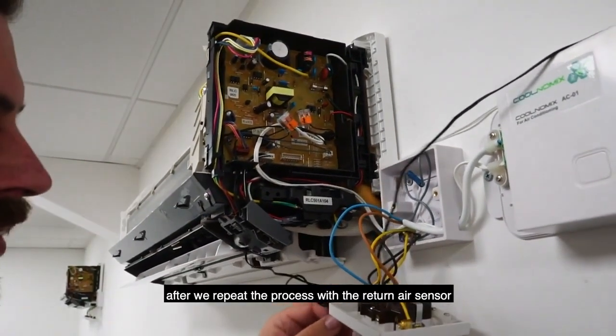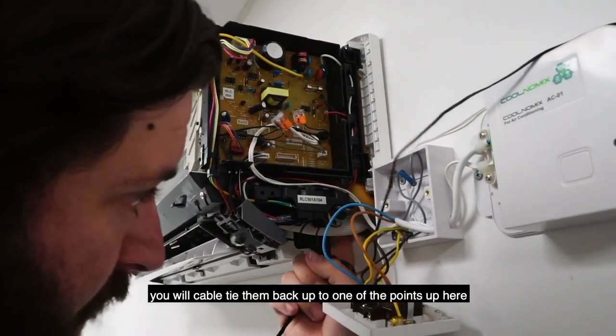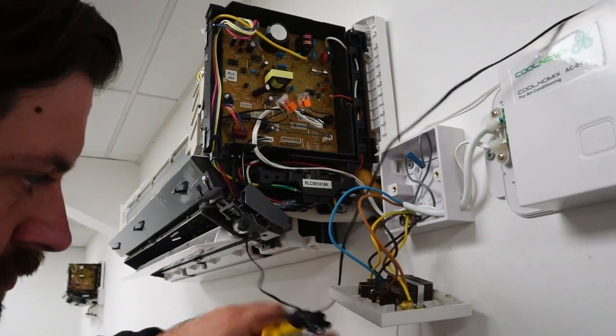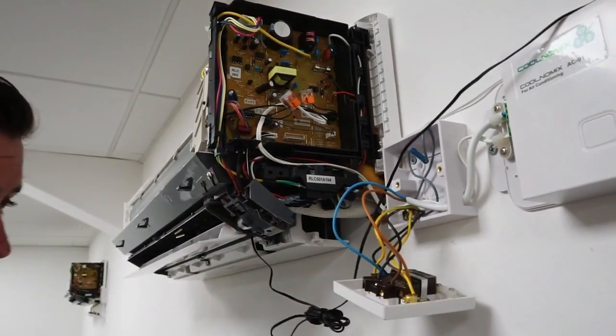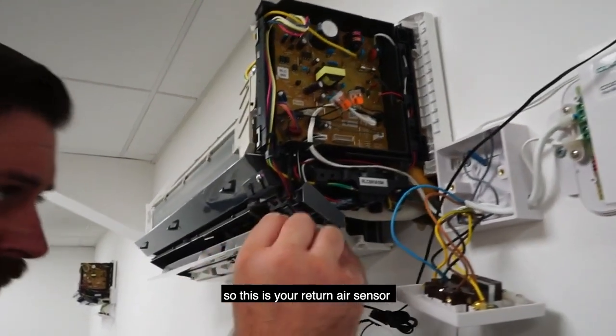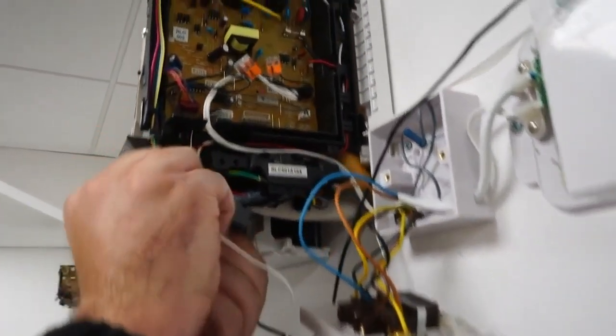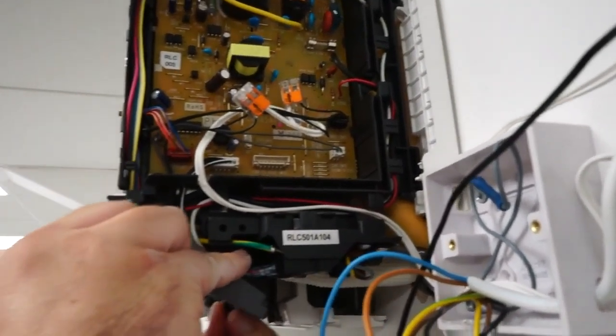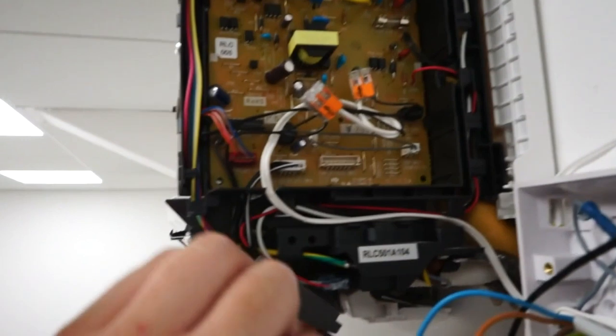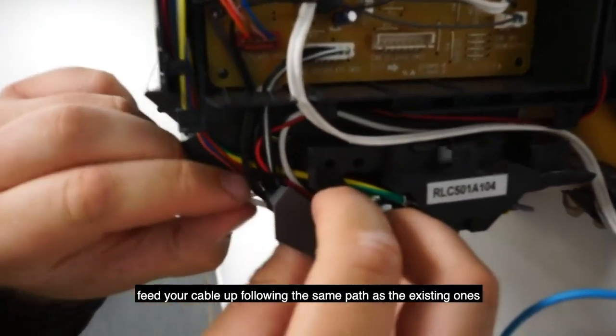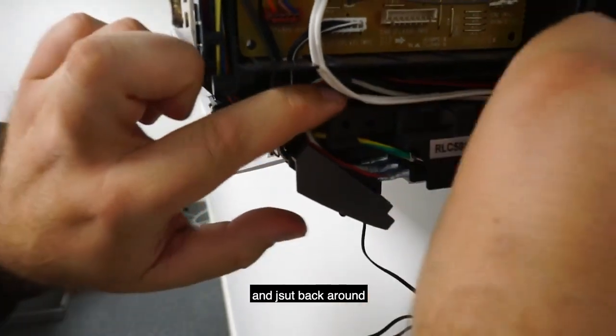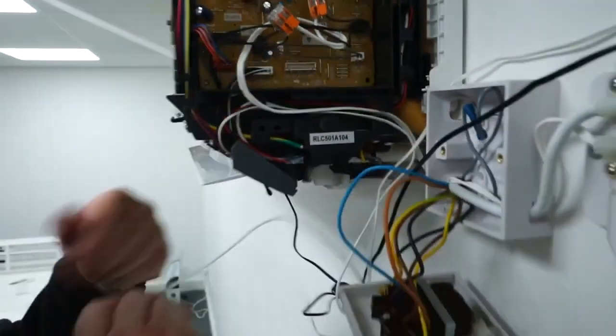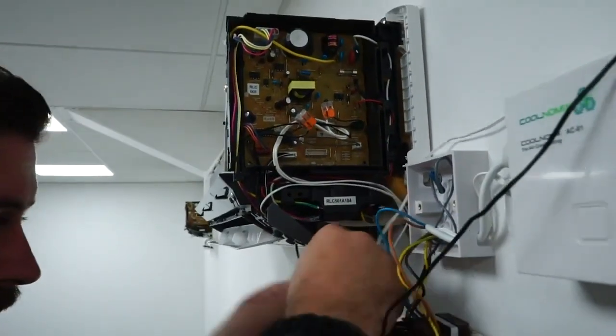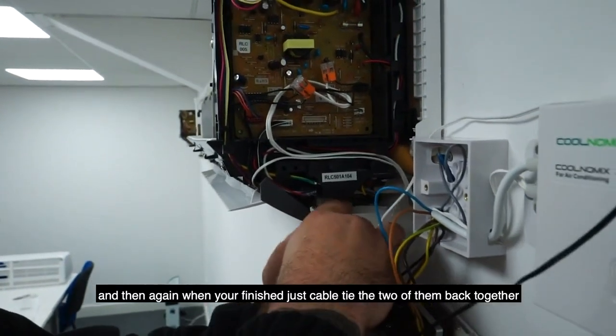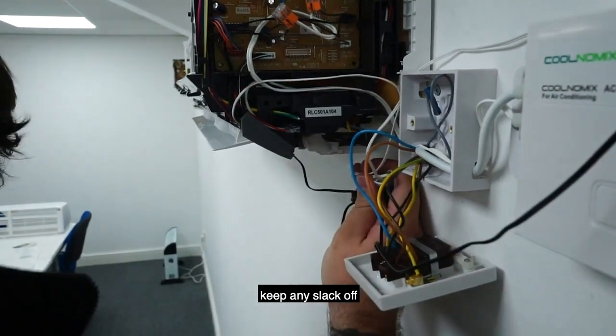After we repeat the process with the return air sensor, you will cable tie them back up to one of the pipes up here. So this is your return air sensor. It will go in situ to the existing return air sensor. Feed your cable up following the same path as the existing ones and just back around. And again, when you're finished, just cable tie the two of them back together to keep any slack off.